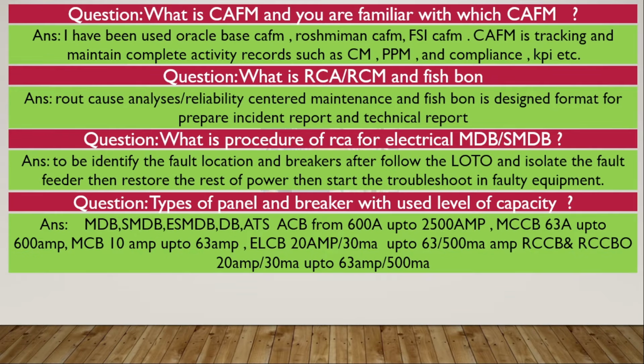Then breakers. ACB, air circuit breaker, can be used from 600 up to 2500 ampere. MCCB, molded case circuit breaker, can be used from 63 ampere up to 600 ampere. Same as MCB, 10 ampere to 63 ampere.